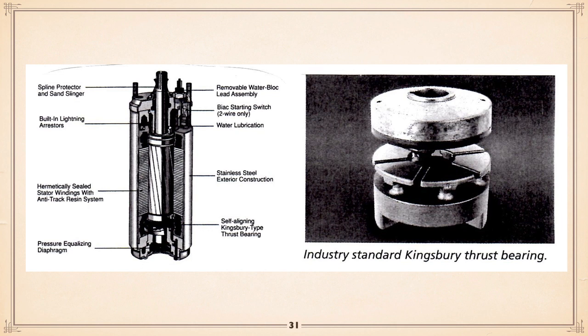Now it says here, self-aligning Kingsbury, so that's why they're pivoting on it. Those, see those little ball things. There's the diaphragm to make sure that the pressure in the motor is the same outside the well. Casing, anti-track resin system. That's what we talk about. They're potted. It's a combination of sand and epoxy and all sorts of wonderful things up there.